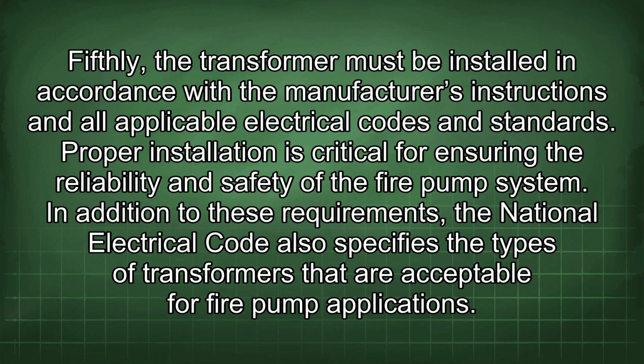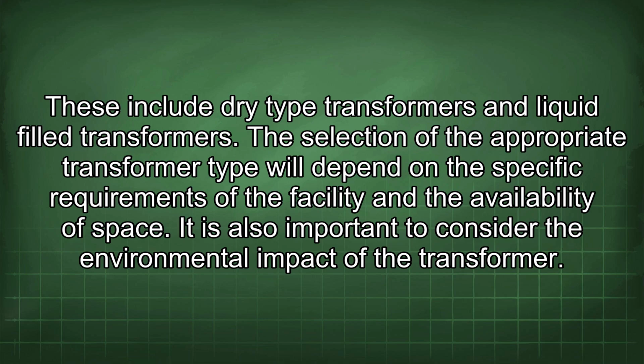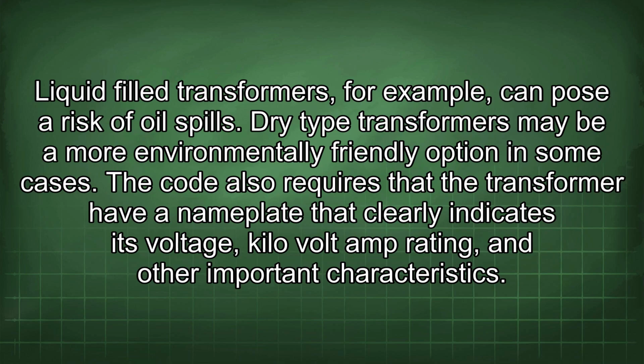In addition to these requirements, the National Electrical Code also specifies the types of transformers that are acceptable for fire pump applications. These include dry-type transformers and liquid-filled transformers. The selection of the appropriate transformer type will depend on the specific requirements of the facility and the availability of space. It is also important to consider the environmental impact of the transformer. Liquid-filled transformers, for example, can pose a risk of oil spills. Dry-type transformers may be a more environmentally friendly option in some cases.